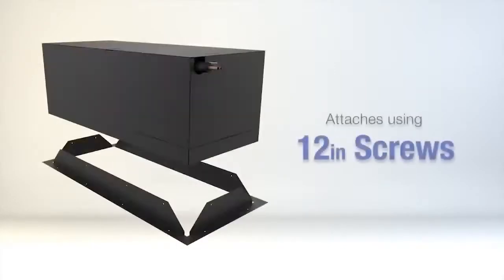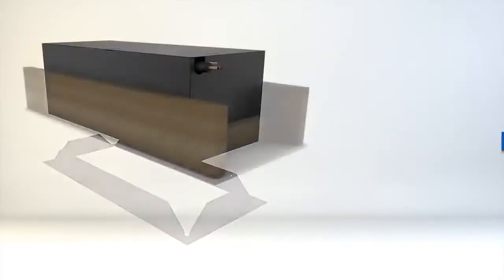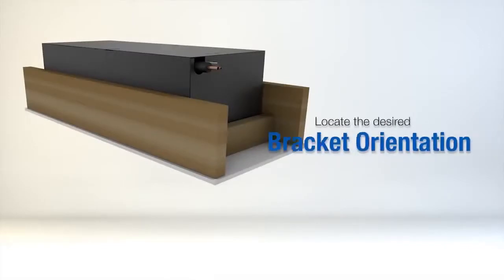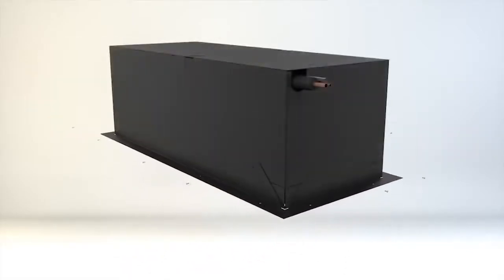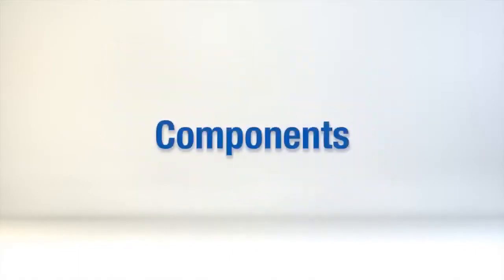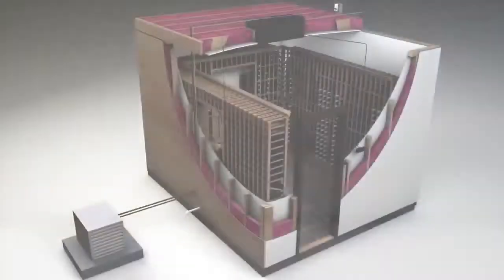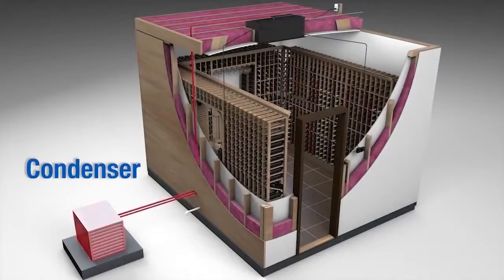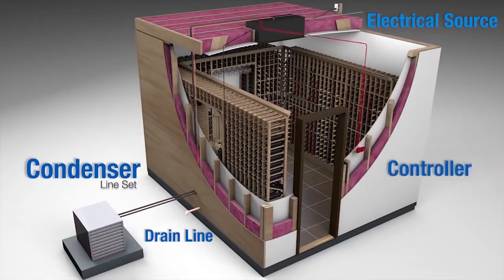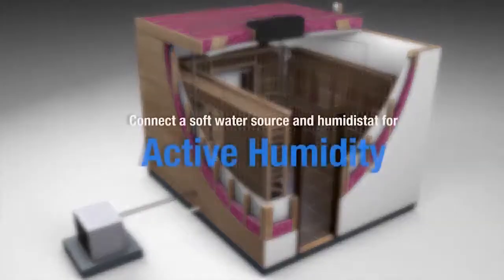The mounting bracket is attached using 12 half-inch self-tapping screws. Locate the desired mounting location and bracket orientation. Slide the bracket over the unit and attach using the screws and pre-drilled hole locations on the unit. There are 5 components that need to be connected to the evaporator unit: the condenser, refrigerant lines or line set, the electrical source, the condensate drain line, the controller, the bottle probe for measuring liquid temperature in the cellar. If the unit is equipped with the active humidity option, you will need to connect a soft water source and the humidistat.